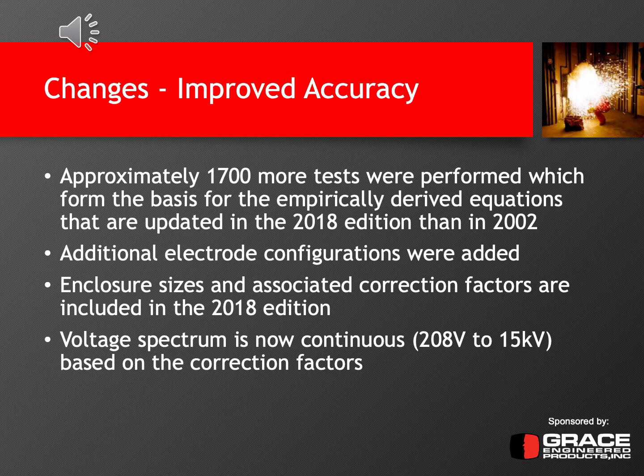Also, the improved model and equations take into account additional factors that weren't in the 2002 edition, such as additional electrode configurations, enclosure sizes with correction factors for that, and the voltage spectrum is now continuous versus just fixed set points. So whatever your voltage is, you can have a correction factor that will more accurately calculate the incident energy most appropriate for that voltage level.